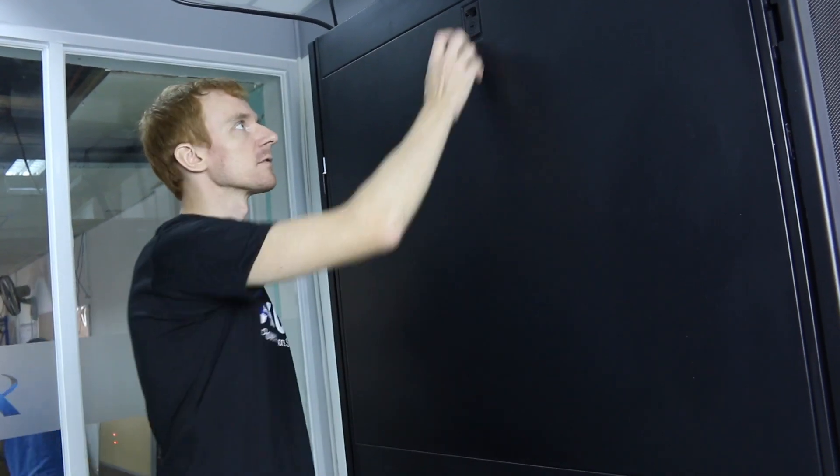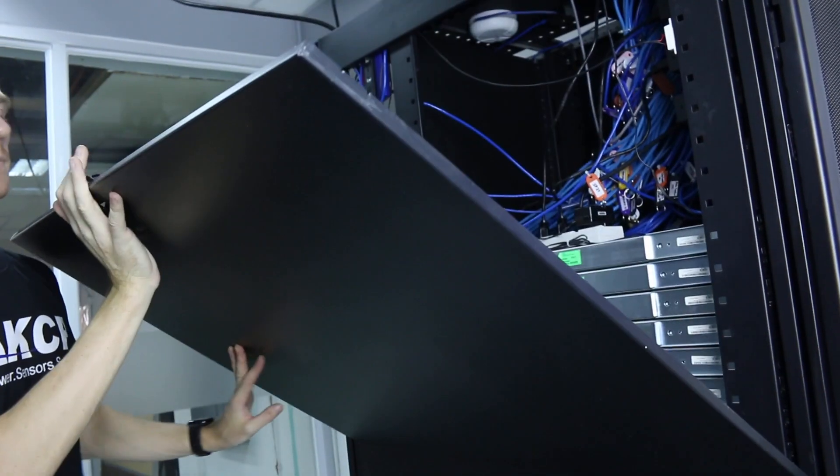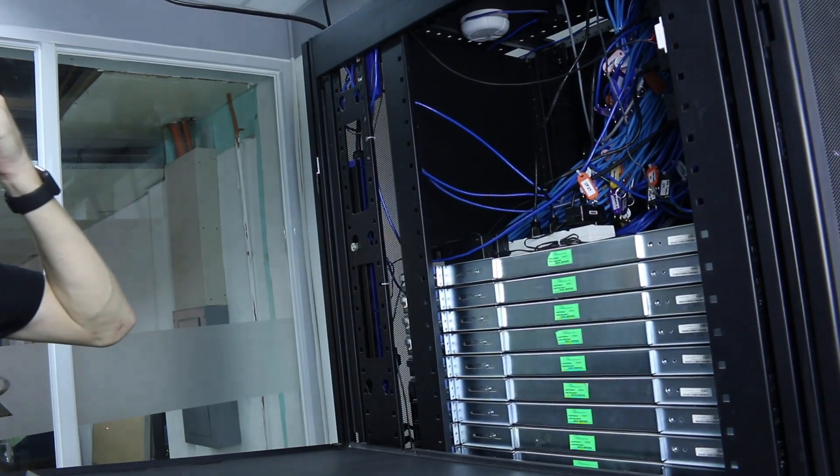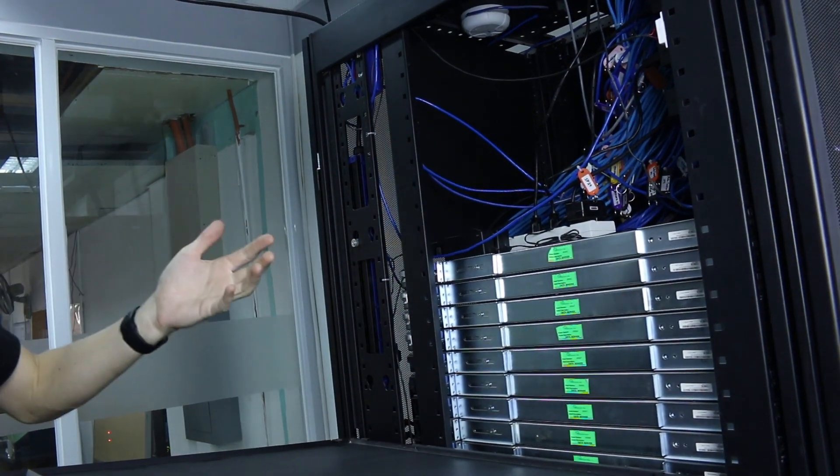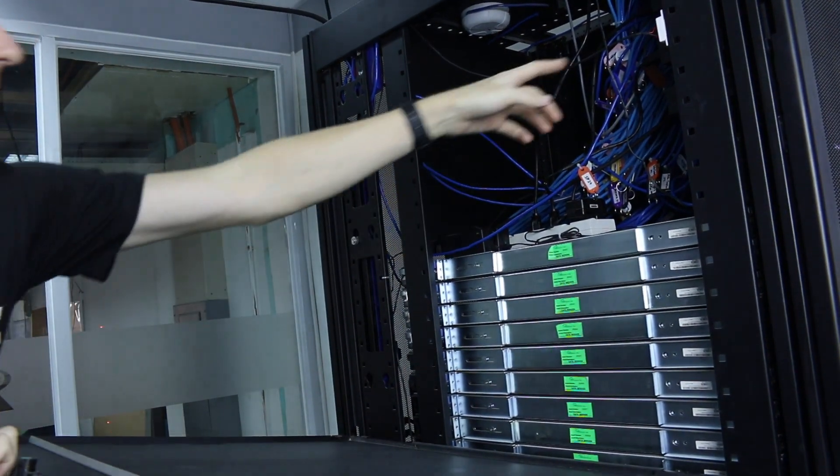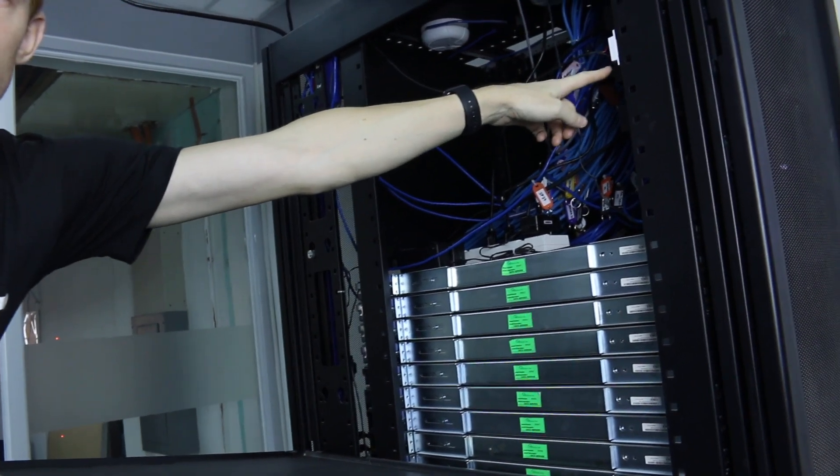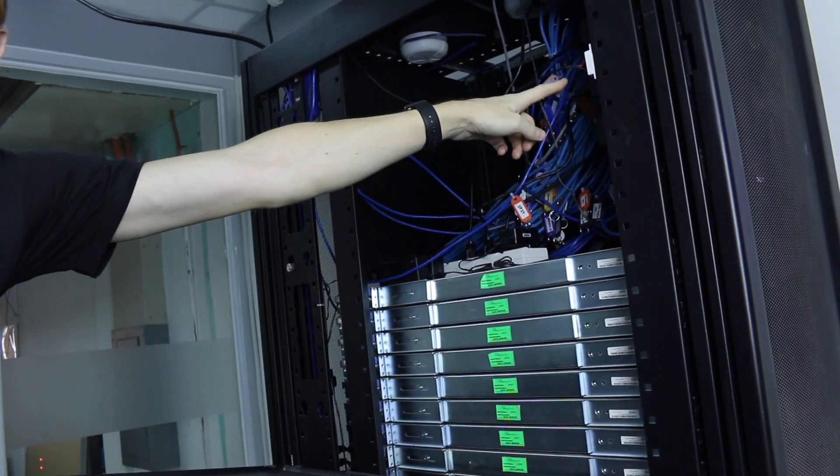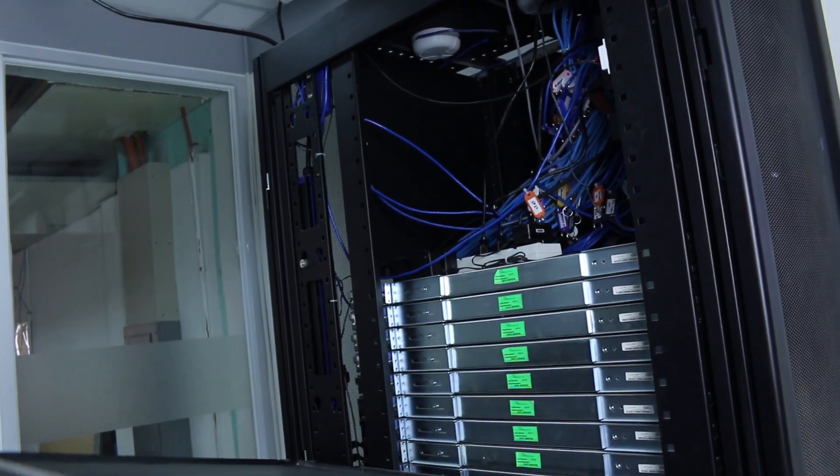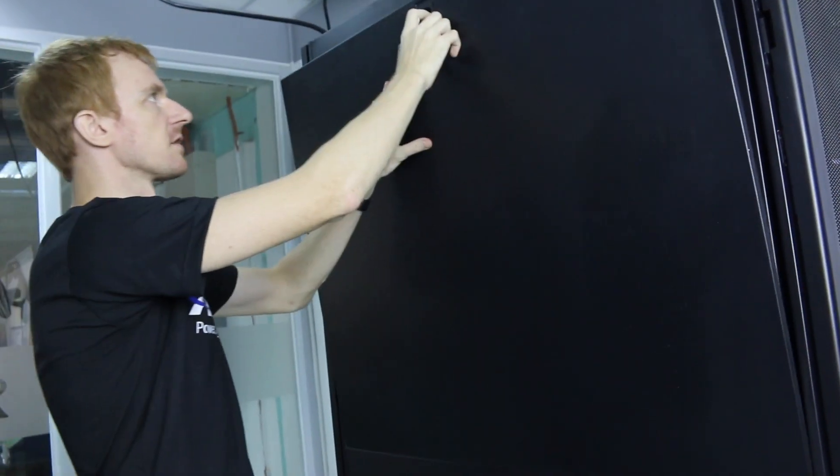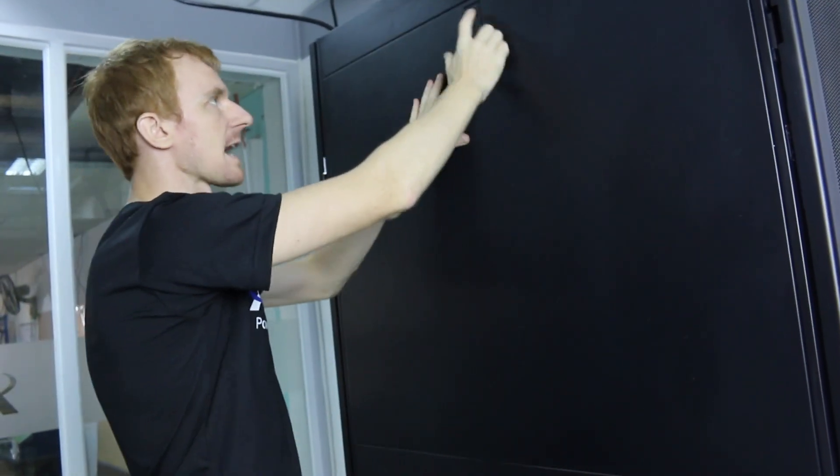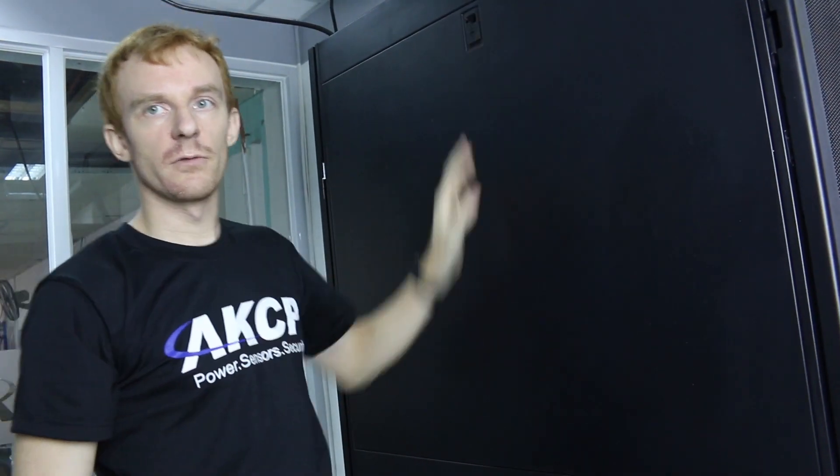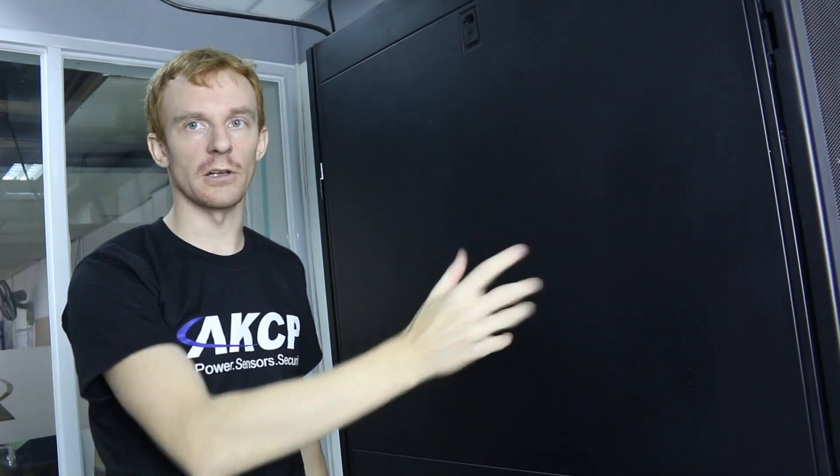Connected to the RFID swing handle locks, we have security sensors that monitor the side panels. Should the side panel be opened unauthorized without somebody first accessing by RFID card, security sensors positioned inside the cabinet will monitor for this condition. If I access the side panel without first unlocking the front door using my RFID card, we could sound an alarm or send an alert that the cabinet has been potentially breached.